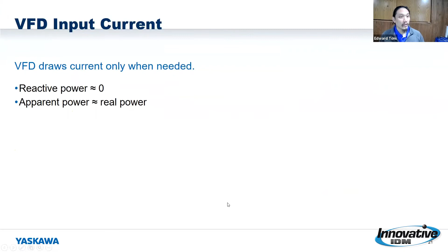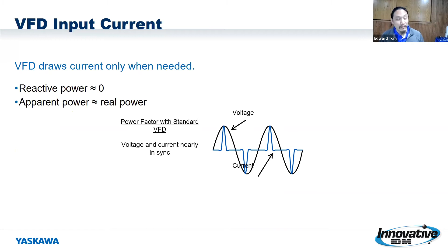That's the power factor improvement. As we take the reactive power on the line and drive it closer to zero, the power that your power company needs to supply is now more closely matched to what you need - no extras they're going to charge you for. So when they charge you for that mug of beer, they're not charging you for the extra foam on top. You're getting more beer coming out, so you get a good drink into your system.